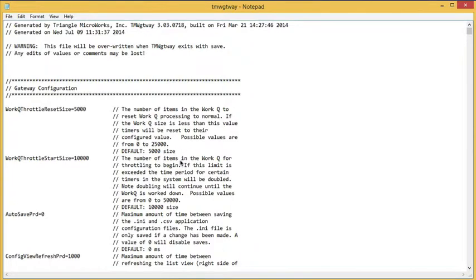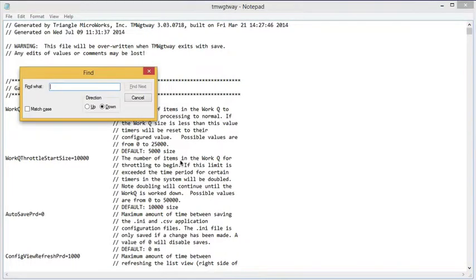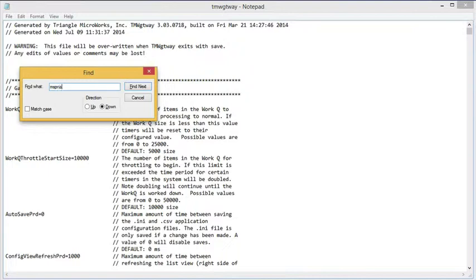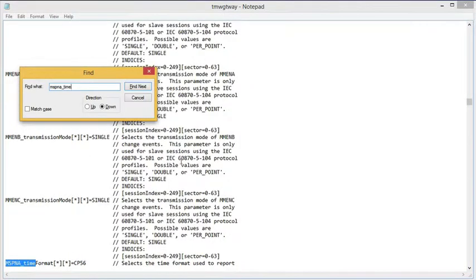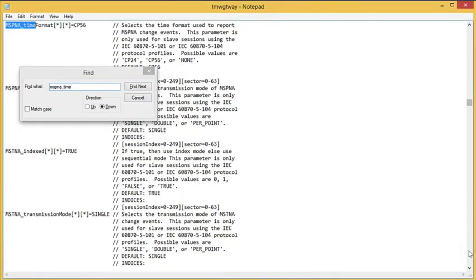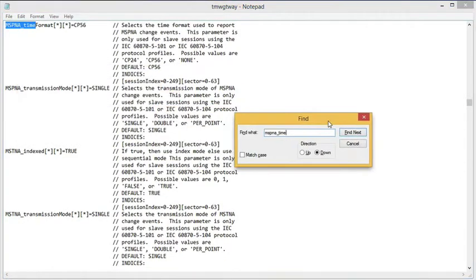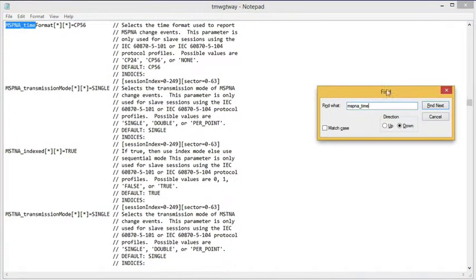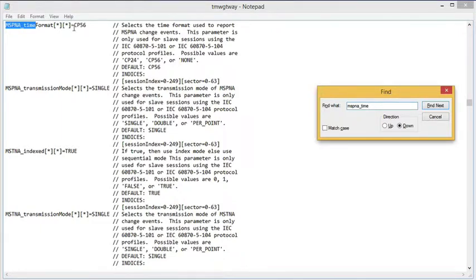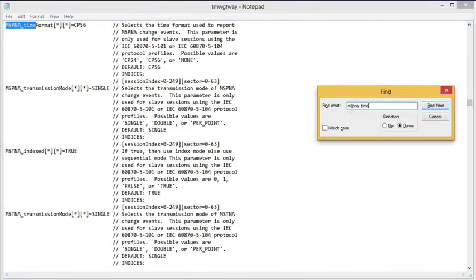And we want to search for a field with the base type. So for example, for the single point MSPNA underscore time format, or you can just use time. This field sets the time format that will be reported by this SCADA data gateway. For a single point, it defaults to CP56, which is a 56-bit time, which is what we want in this example.